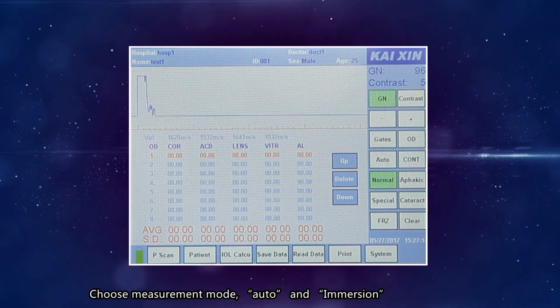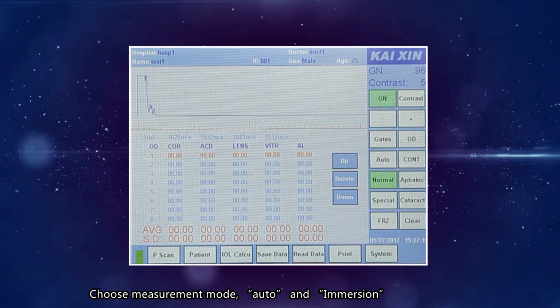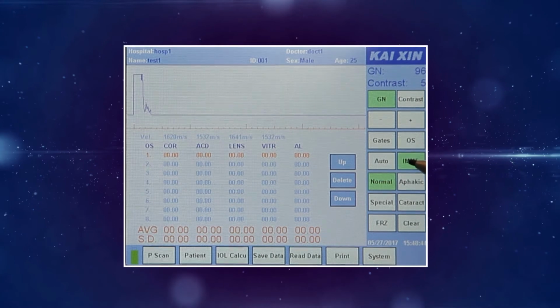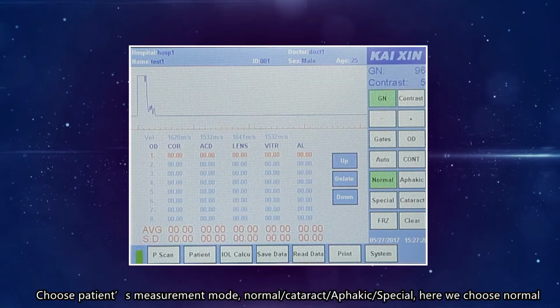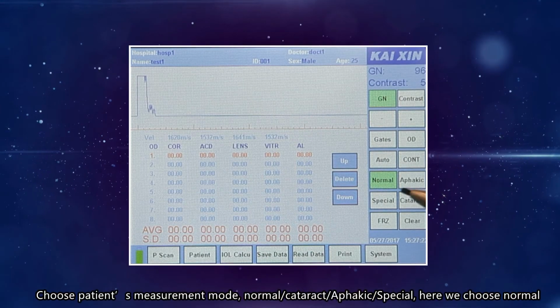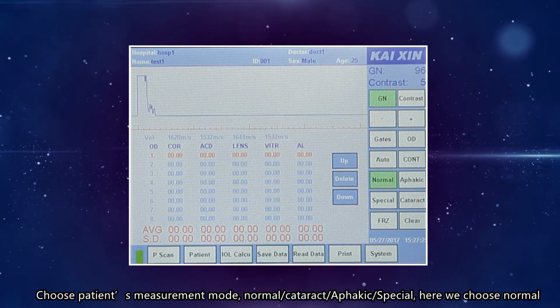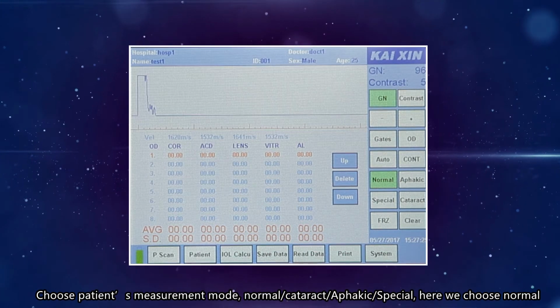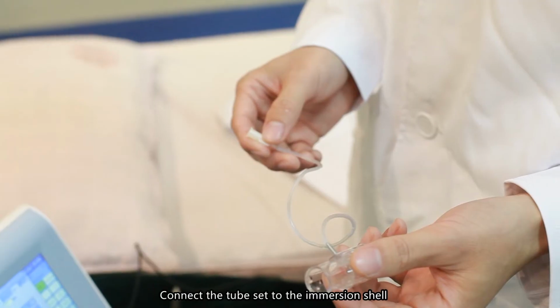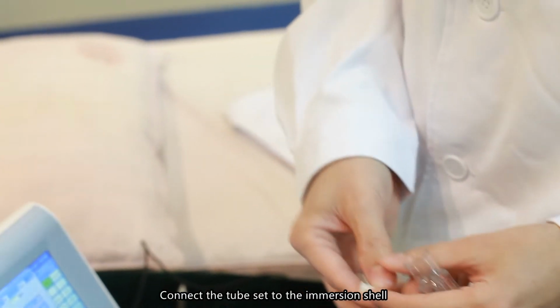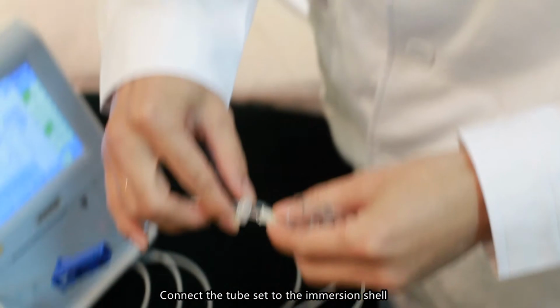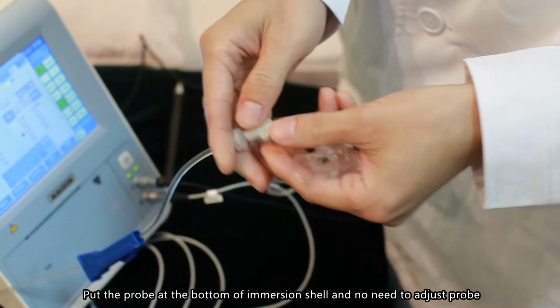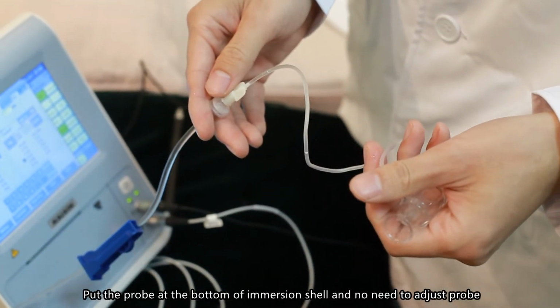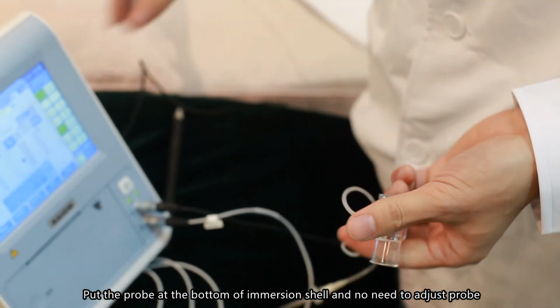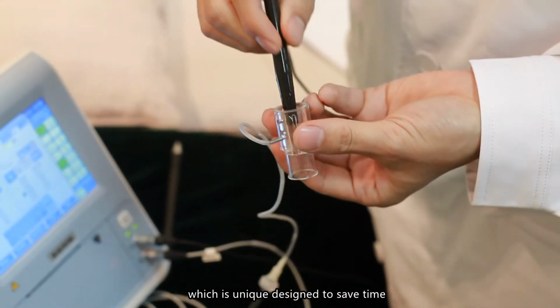Immersion mode. Choose Measurement mode, Auto and Immersion. Choose Patient Measurement mode, Normal, Cataract, Aphakic, Special. Here we choose Normal. Connect the tube set to the immersion shell.